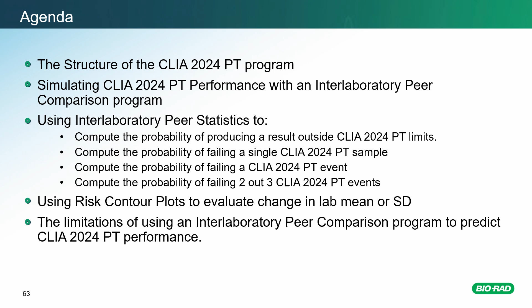So the CLIA 2024 PT program consists of 3 events a year, and each event has 5 unknown samples. The PT samples are supposed to be treated exactly like you would treat a patient specimen. So for instance, if you have 4 different instruments that are testing a single analyte, you don't test the PT sample on all 4 instruments, unless that's what you're doing with patients. So you treat the PT sample exactly like a patient, and then it's scored according to the performance specification.